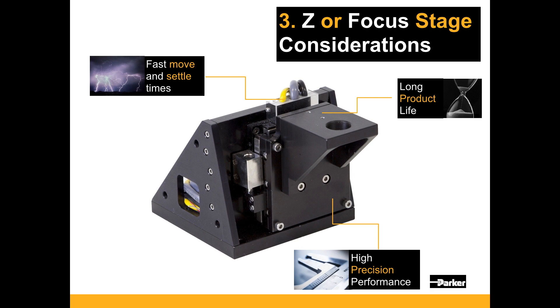The Z-axis stage is quite possibly the most difficult motion element to the instrument. Since the slides and material on them are not flat, this stage needs to make extremely quick, short moves to maintain focus. These moves are typically on the order of 10 microns, and the stage must settle to within 0.5 to 0.1 microns depending upon the level of magnification, and must settle within 20 milliseconds to maintain high throughput.